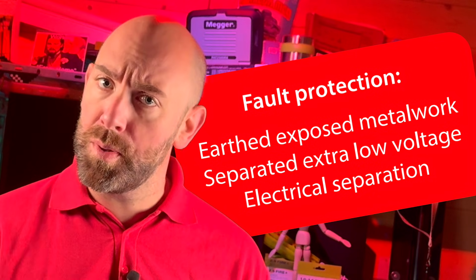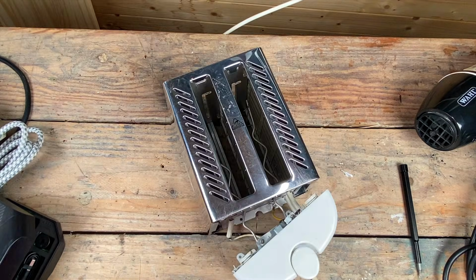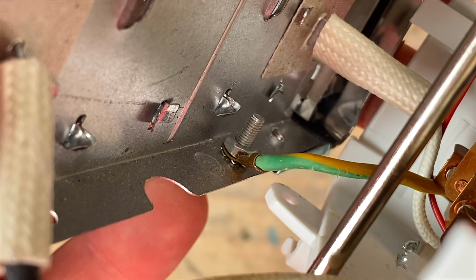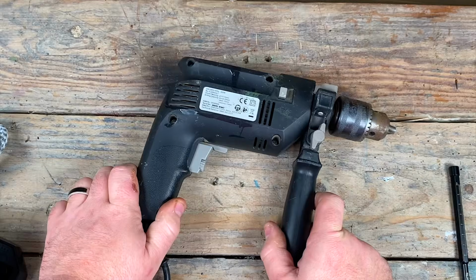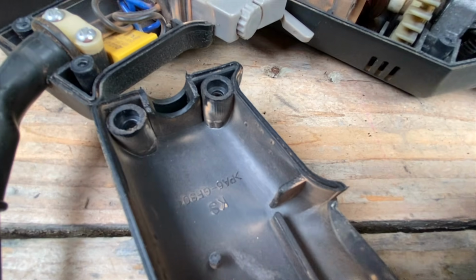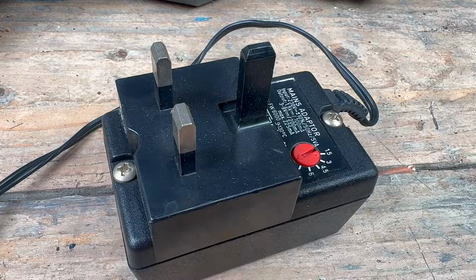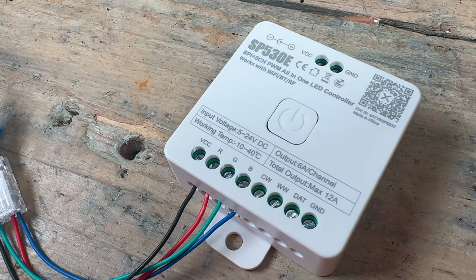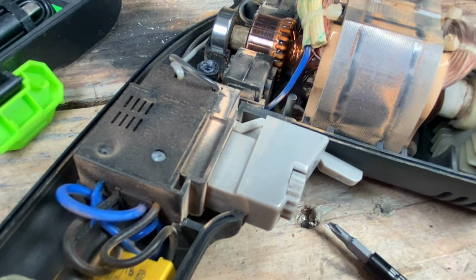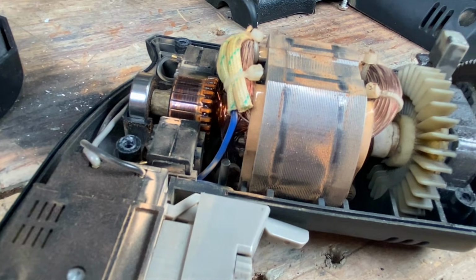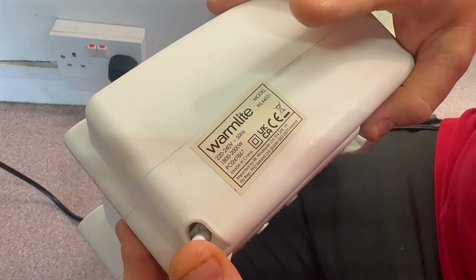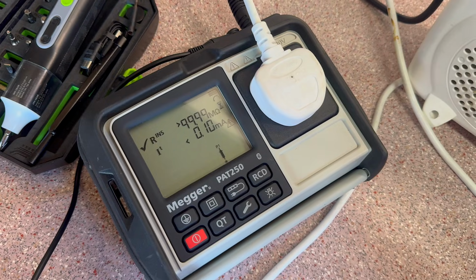The second is fault protection. This steps in if the basic protection fails. Fault protection might involve connecting metalwork to earth, enclosing live parts inside an insulating case, electrical separation from earth, or supplying the equipment from an extra low voltage source. Some electrical equipment uses a single layer of reinforced insulation that offers both fault and basic protection. The type of protection built into the electrical equipment determines its classification, and that classification tells us exactly what test we should carry out. Okay, so with that foundation, let's start with the most common classification category, Class 1.